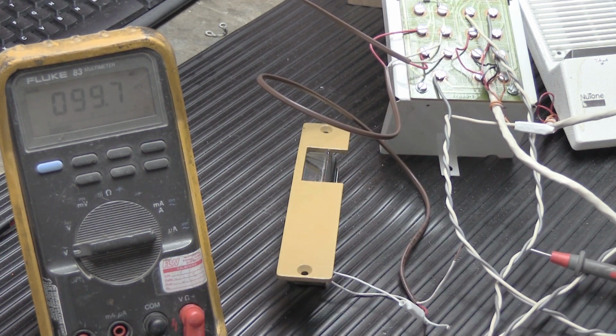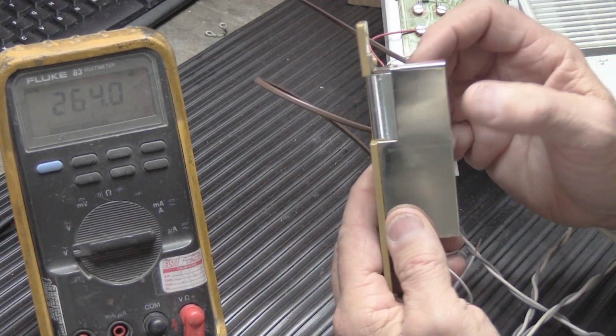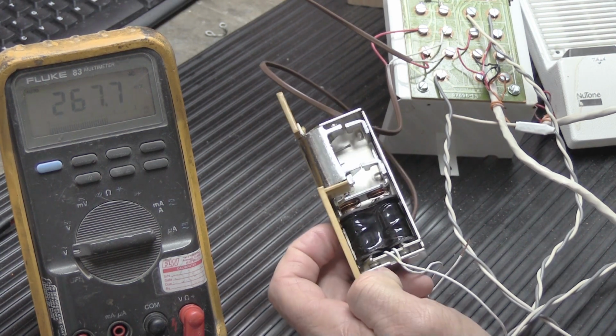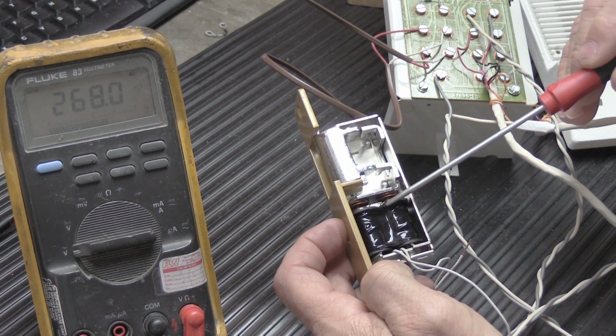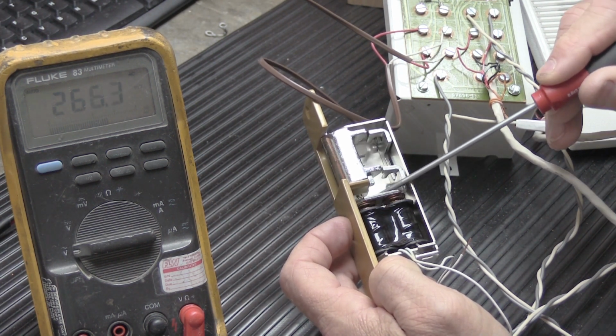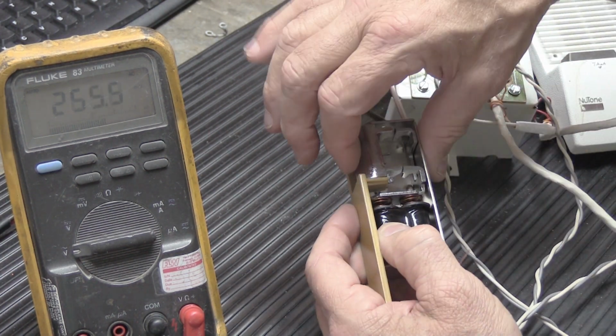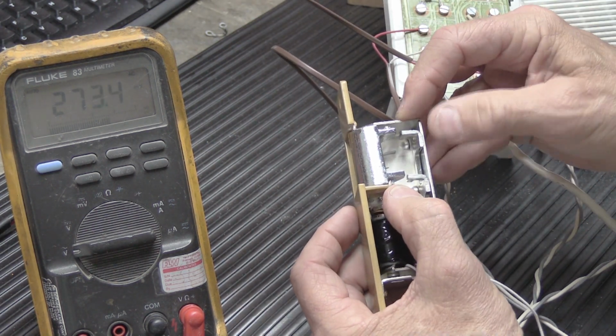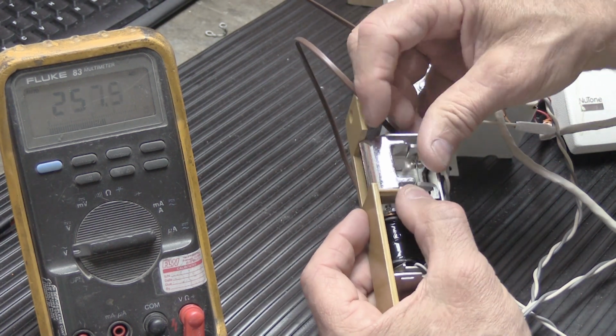A door release is a fairly simple electromechanical device. Essentially what you have inside here is, open this up. In this particular one, we have 2 electromagnetic coils with plungers and springs. When it's energized, it pulls this plate down. And as it pulls it down, when it's in the upper position, it locks the latch, so you can't force it open. When it pulls it down, it moves these arms out of the way and allows the latch to flip open.